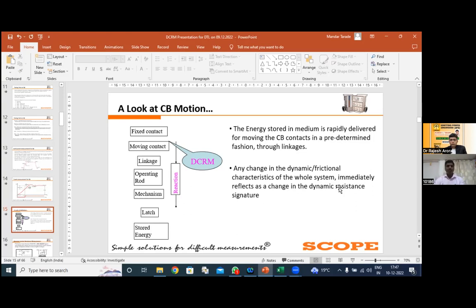It is very important that the linkages also play a significant role, because whenever your mechanisms are moving, accordingly the linkages are moving and making and breaking the contacts. From the instrument, you directly get the mechanism travel. But if you need to calculate the contact travel, then the linkage ratio plays a very significant role, because the contact travel is nothing but the mechanism travel multiplied by the linkage ratio. So at the time of performing the travel operation, feeding the linkage ratio is very important to get the exact contact travel.